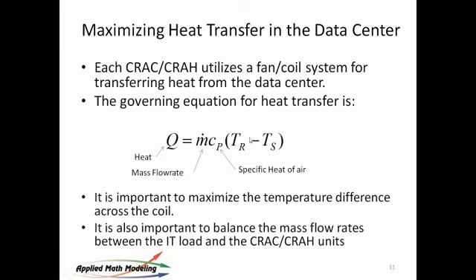Delta T is the return supply difference. So the cooling system and the computers themselves respond to the same equation. They are exactly the same. And you see here we've got a mass flow rate number that's quite important. We'll talk a little bit more about that as we go along. But, of course, the supply and return deltas are important as well. If mass flow rate is too high, the delta T is not so good on a cooling system. And we'll talk about that and illustrate that in a moment.